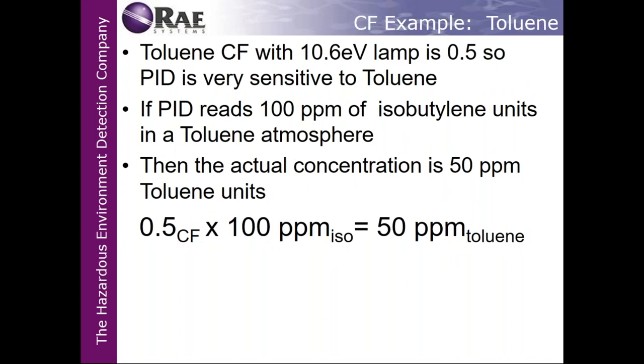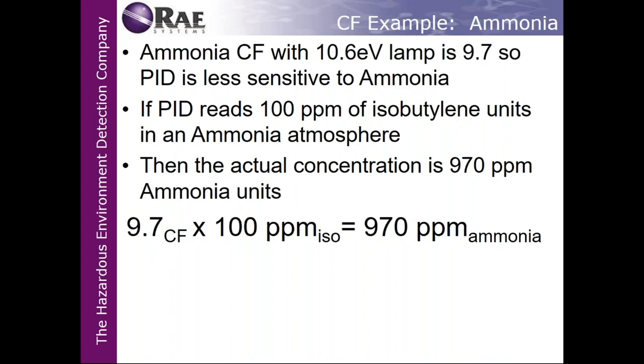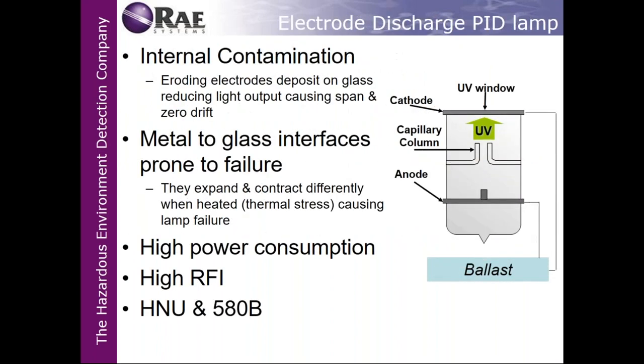In this case, toluene's correction factor with a 10.6 lamp is 0.5. So a PID is very sensitive to toluene, very similar to what my example was just then. If a PID reads 100 in isobutylene units, then with the correction factor of 0.5, you're reading technically 50 ppm in toluene units. Now, on the contrary, with ammonia with a 10.6 lamp, its correction factor is 9.7. I usually move it up to about 10.0. If a PID reads 100 in isobutylene units, 10 times 100 is 1,000 parts per million, roughly, I should say. So I hope these two examples help you understand the differences between using correction factors and using just the isobutylene scale.